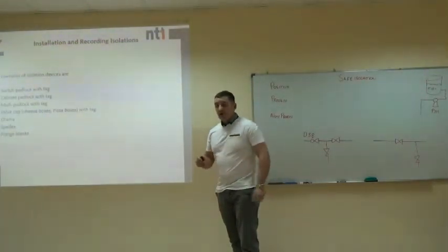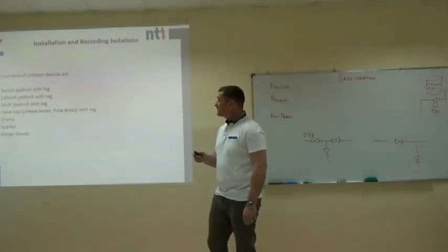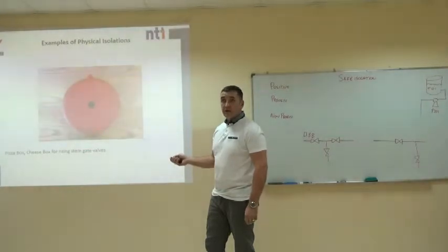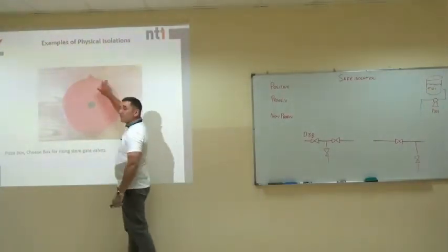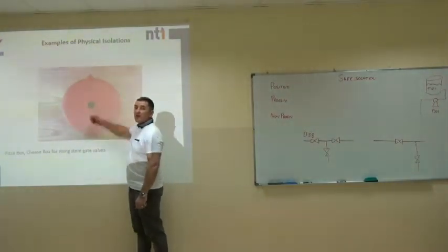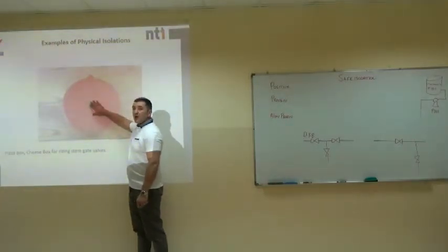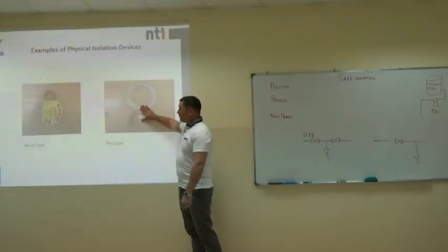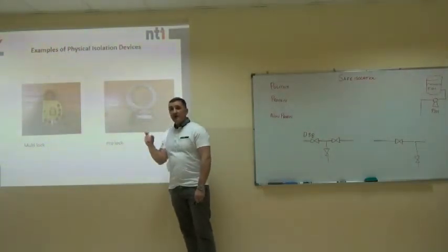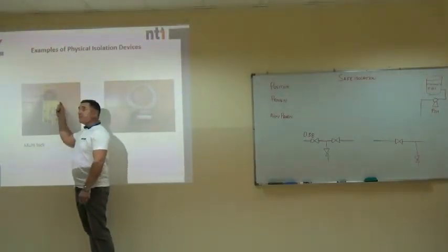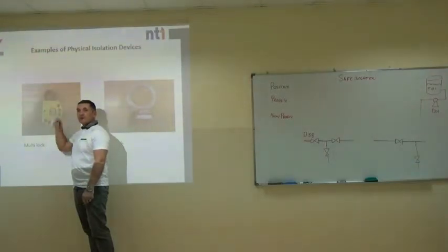We should never use emergency stop buttons or switches as isolation devices. All electrical isolations should be isolated properly. Examples of isolation devices — in the UK we call this a pizza box, cheese box, or baby bell. This is designed to go around the wheel of a gate valve, with a hole in the middle for the rising stem, enabling the valve to be locked in an open or closed position. Multi-locks and wire locks are quite good for valves. During a shutdown, every tradesperson puts their own lock on, and the Permit to Work Authoriser puts theirs on as well. Once all tradespeople have been removed from the permit, the Permit to Work Authoriser withdraws their lock last.